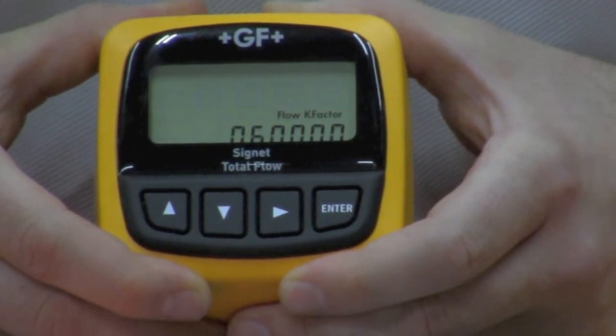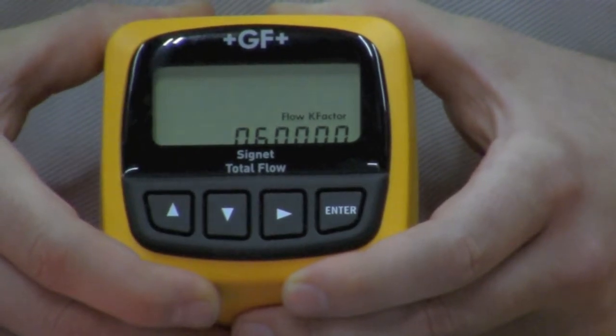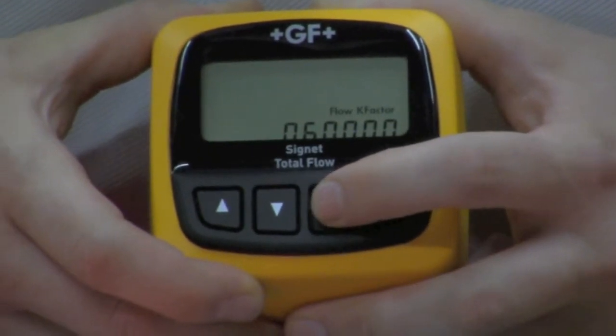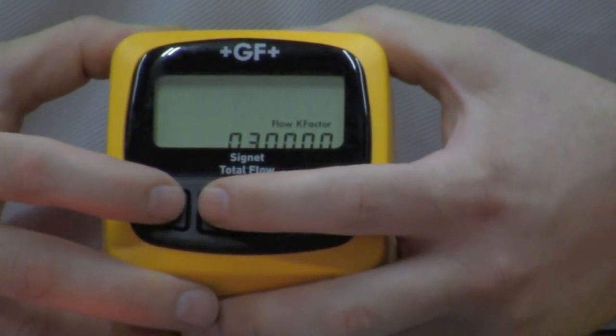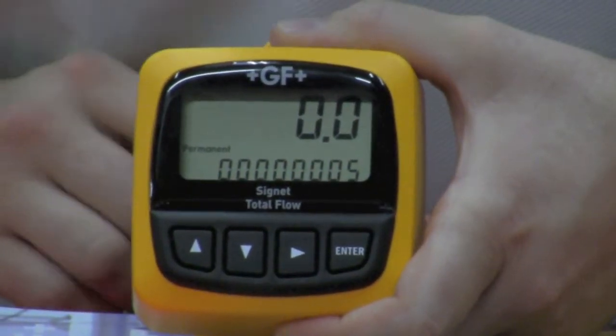Supplied with your Signet fittings is a k-factor for your specific flow meter and your specific line size. In order to adjust the k-factor, we can use the enter button, the up arrow, and the down arrow. This will back you up to the previous menu no matter where you are within the main menu or the programming menu. For a more in-depth look at programming, please see our programming video on the 9900.